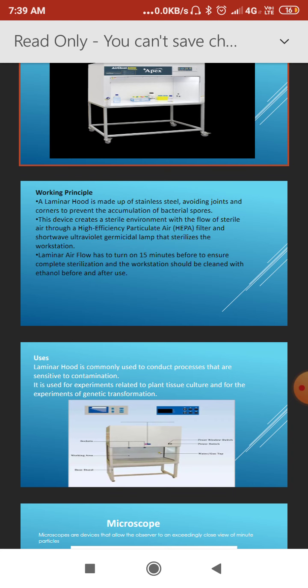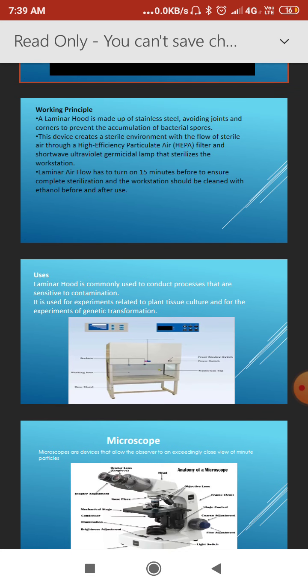For the vertical type, the main HEPA filter is placed immediately above the working area. Clean air is blown normally at 0.35 meters per second vertically down over the surface area. By this way, laminar airflow can eliminate all types of bacteria.